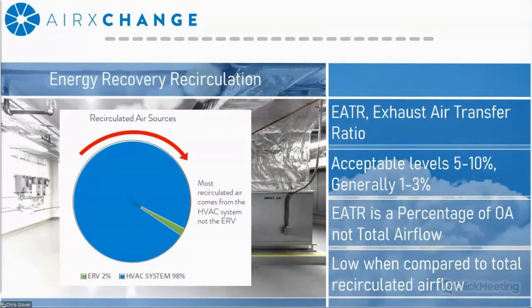Per the ventilation standard, you're allowed to recirculate a certain percentage of air depending upon the class of air you're exhausting. Those levels are 5 and 10% depending upon the class of air. However, most modern designs have recirculation rates that are usually well below that, somewhere in the 1 to 3% area. And it's really important to keep in mind that EATR is a function of outside air, which is usually the lower of the two airstreams when you can compare outside air to recirculated air and calculating your total system delivered air. So it's essentially a small percentage of the smaller airflow.